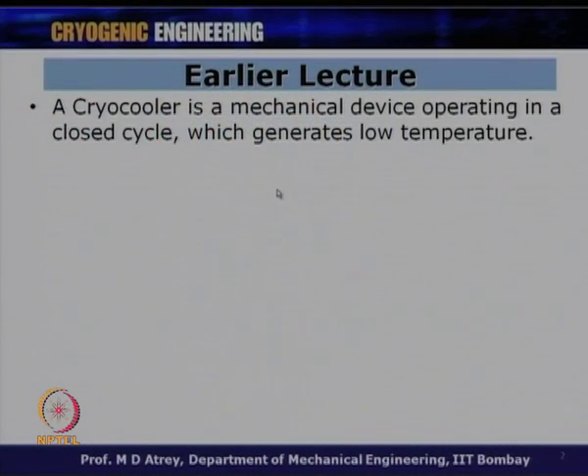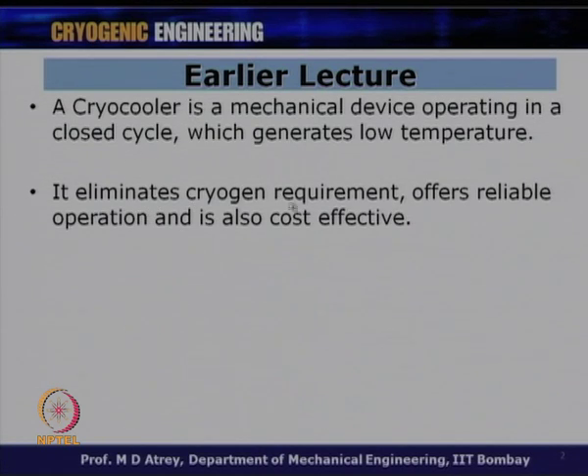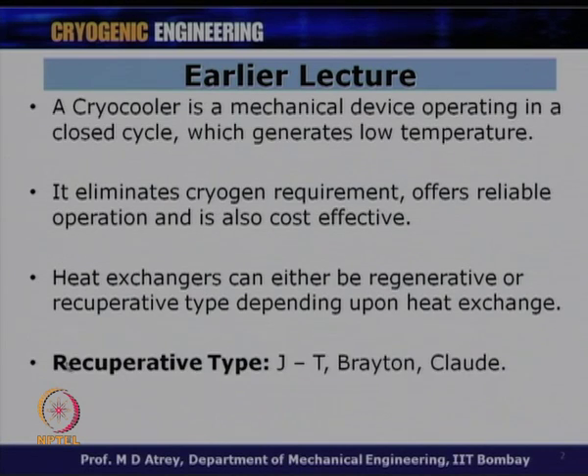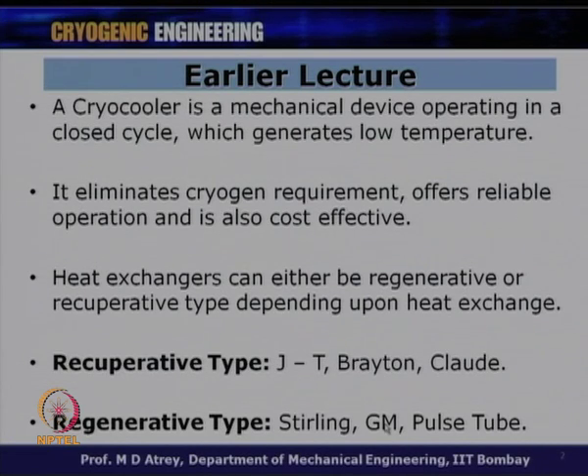A cryocooler is a mechanical device operating in a closed cycle manner which generates low temperature — comparable to a domestic refrigerator. It eliminates cryogenic liquid requirements, offers reliable operation, and is cost effective. Heat exchangers in cryocoolers are either regenerative or recuperative type. Recuperative types include Joule-Thomson, Brayton, and Claude cryocoolers; regenerative types include Stirling, Gifford-McMahon (GM), and Pulse Tube cryocoolers.